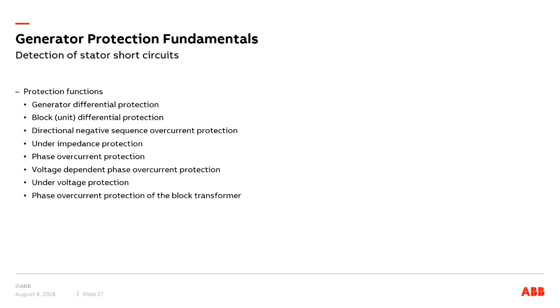So how do we detect stator short circuits? There are a number of different kinds of protections capable of detecting and initiating trip in the case of a stator short circuit. The one important and the foremost is the generator or unit differential protection. This is commonly used for all generators, typically above about 2 megawatt size of generator. And the directional negative sequence overcurrent protection can operate as a fast protection for unsymmetrical short circuits in the generator.